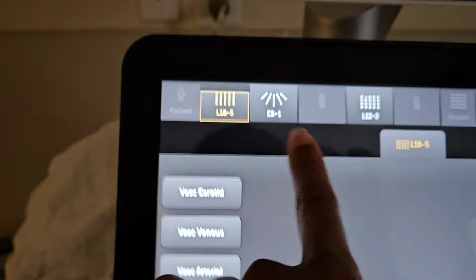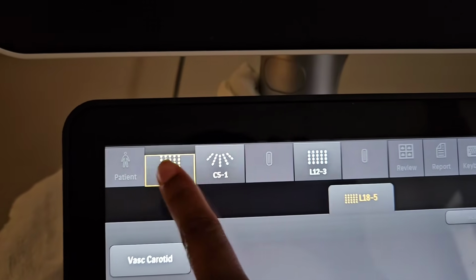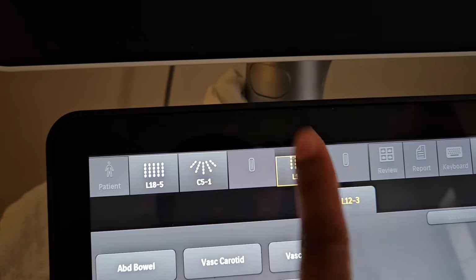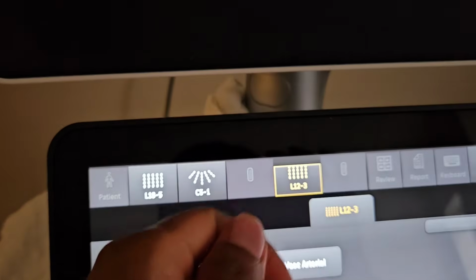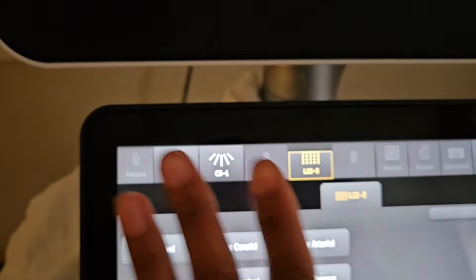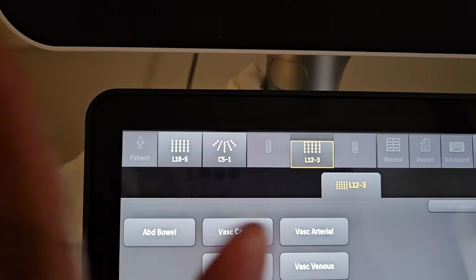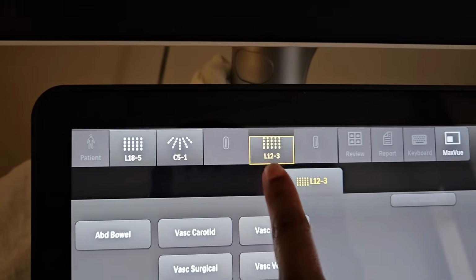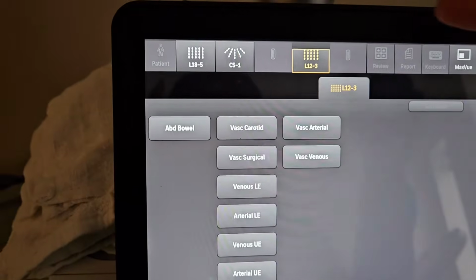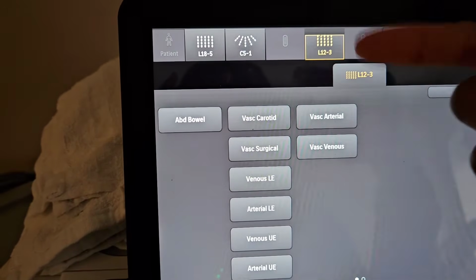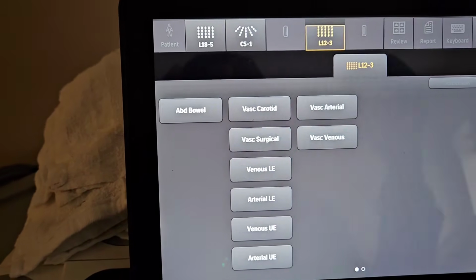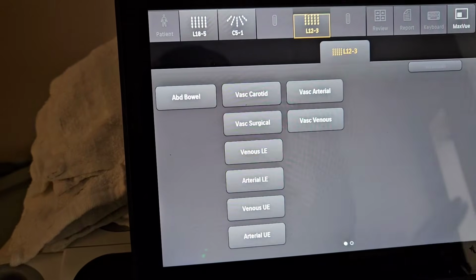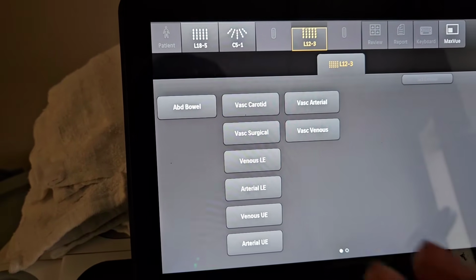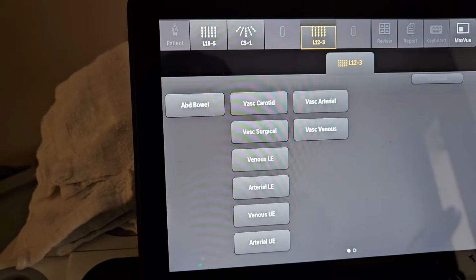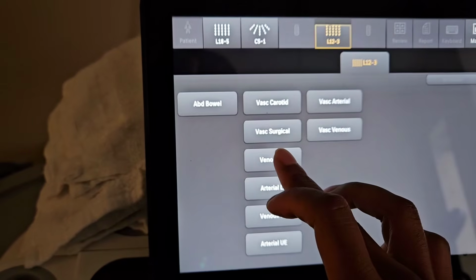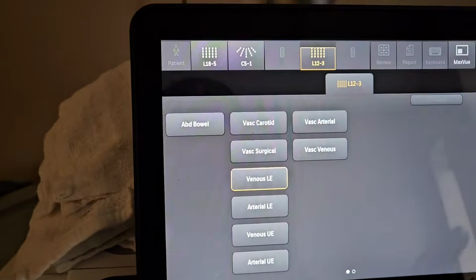First, you select which transducer you're going to use. Each one will have a button or a switch on the machine. Each machine is different. I'm just going to show you this machine. Let's use the L12. Next, after you select the transducer, you have to select an exam preset. This adjusts the gain and the different settings for each type of exam that you're going to do. I'm going to select venous lower extremity.